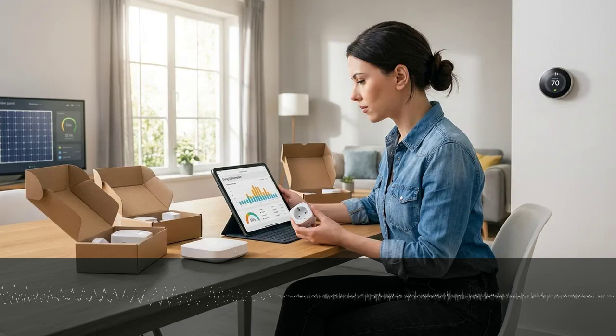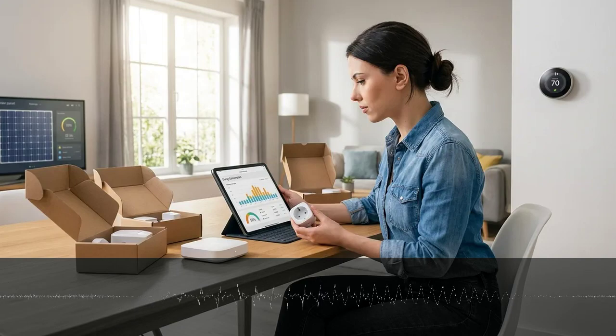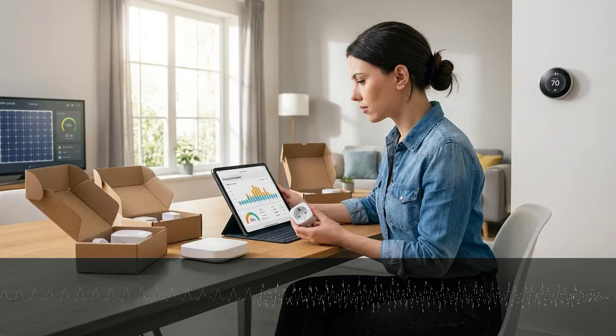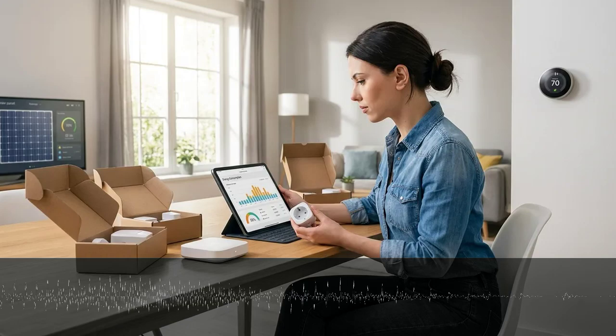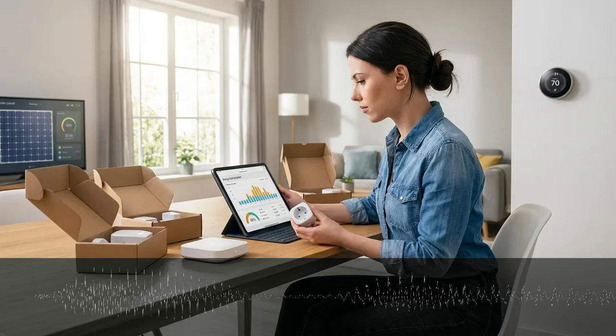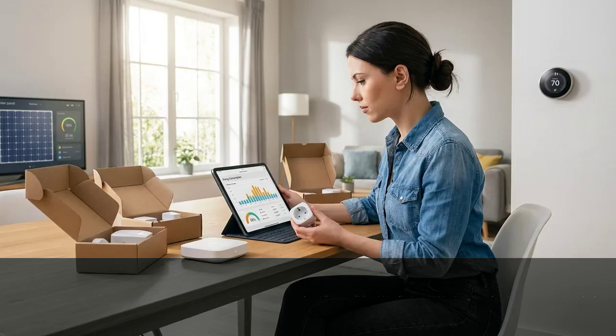Implement graceful degradation for sensor failures. Your energy automations shouldn't crash when a sensor battery dies. Fallback logic looks like this. If occupancy sensor state equals unavailable, then use fallback schedule, which is preset times for HVAC and lighting, and notify user that occupancy sensor is offline and using scheduled fallback. Otherwise, use occupancy-based automation. This is critical for HVAC control. A failed sensor shouldn't leave you without heat. Test your fallback behaviors by disconnecting sensors and verifying automations execute correctly.